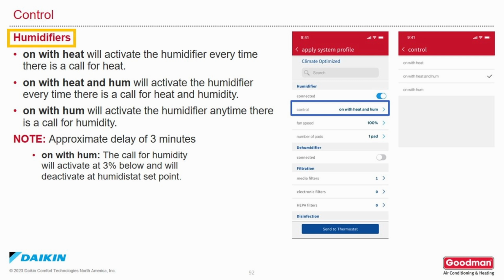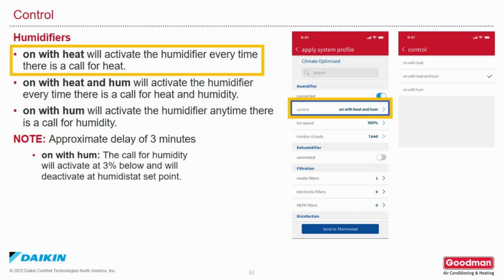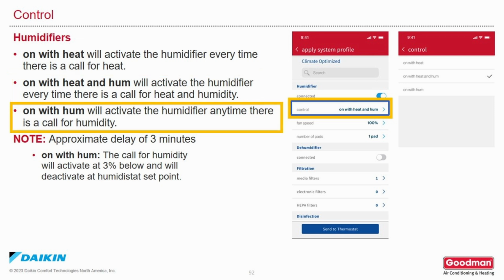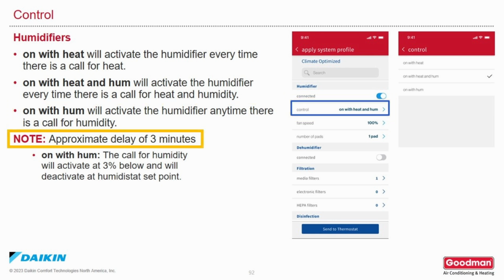When you're setting up the control for humidifiers, on with heat will activate the humidifier every time there's a call for heat. On with heat and humidity will activate the humidifier every time there's a call for heat and humidity. On with humidity will activate the humidifier anytime there's a call for humidity. Approximately 3 minutes is the delay time. On with humidity, the call for humidity will activate at 3% below set point and will deactivate at set point.